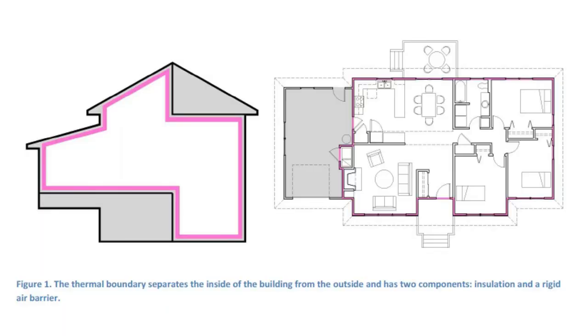Keep all ductwork inside the thermal boundary of the home. On these images, no duct should be found in the gray areas based on how the building envelope for this home has been defined. Never put ducts in a garage. Fresh air intakes need to be above the snow line and 6 to 10 feet from a contamination source or exhaust. Keep wind direction in mind when considering placement.